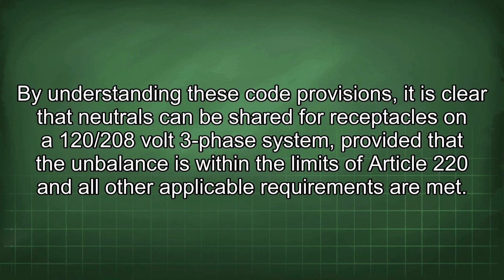By understanding these code provisions, it is clear that neutrals can be shared for receptacles on a 120/208 volt three-phase system, provided that the imbalance is within the limits of Article 220 and all other applicable requirements are met.